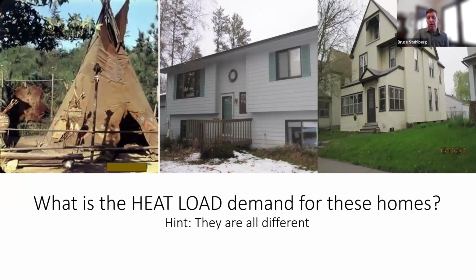So part of all of this is sizing. When you get a new furnace, it can be sized by how many BTUs, or in this case too, with the tonnage of cooling, what's it going to provide, what size it is. And historically speaking, everything has been oversized. The industry just always wanted to make sure that it covered itself, so they were oversized. And oversizing isn't very good.